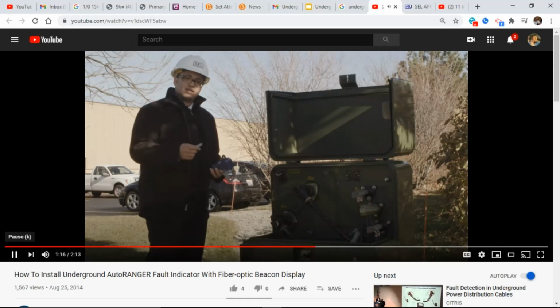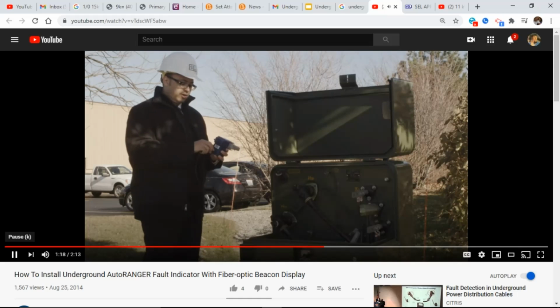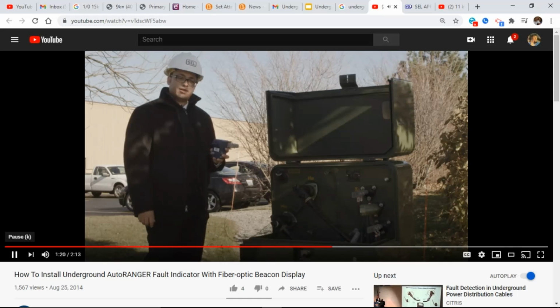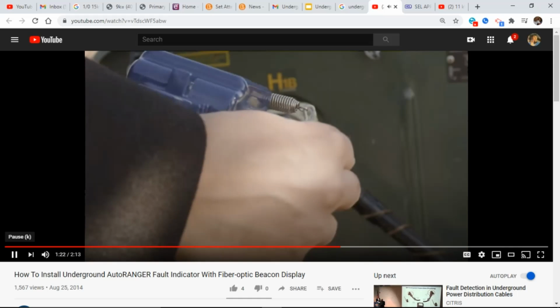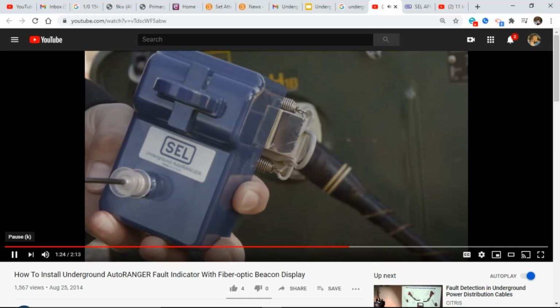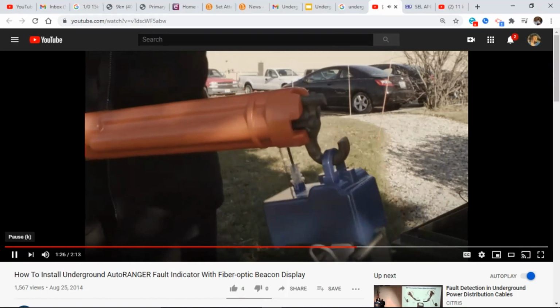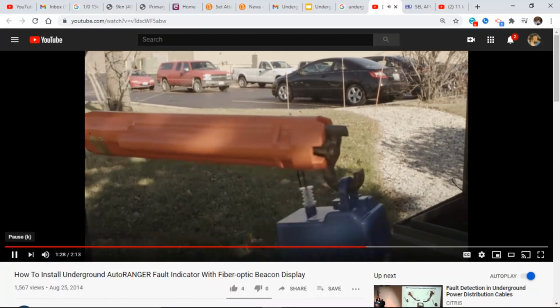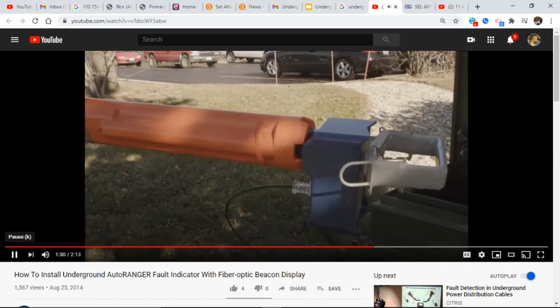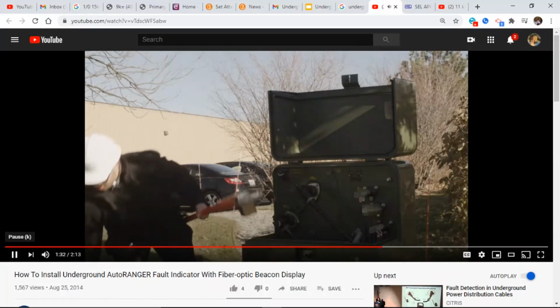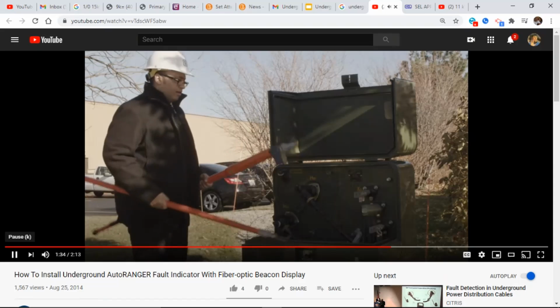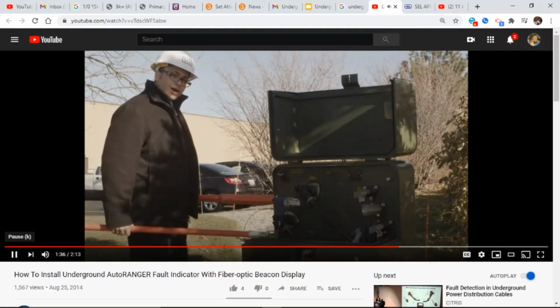So I'm going to now take the display lens and attach it to the faulted circuit indicator. It snaps right into place. Then I'll open the core slightly. I can now attach the fault indicator to my hot stick tool. Now for this installation, we're going to use 2 hot stick tools, and I'll position the sensor.